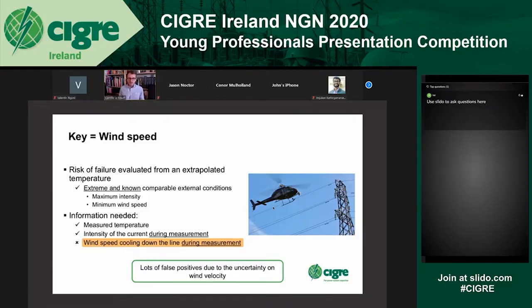The last thing we need is the component of the wind velocity that is effectively cooling down the line at the moment we do the infrared measurement. This is tricky because the infrared camera is usually mounted on a helicopter, and you cannot really install an anemometer on the helicopter that gives a precise measurement. So what people do is ask the pilot to give an estimate of the wind velocity.